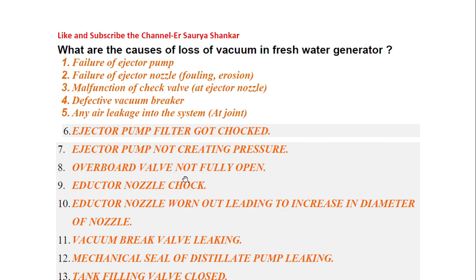Overboard valve not fully open — this is a main one to consider. Sometimes we tend to forget it because all the things are at the top and we are working there, but this valve may be at the bottom platform and you may forget it.